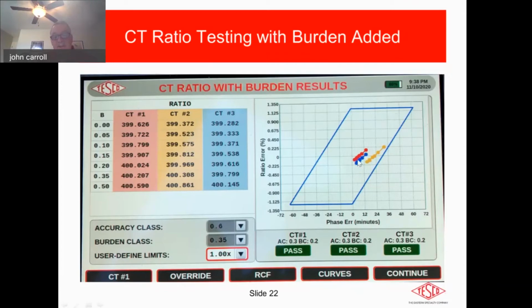And you can see the little clusters that we have on the right-hand side inside that parallelogram are based around the 2 zeros, which is the 0 ratio error and the 0 phase error. So as those two values become evident to us, we can plot it. And we can plot it over each dependent burden. So the only thing changing in this case is the burden, which increases them. So it's a very good, accurate, reliable, repeatable test.